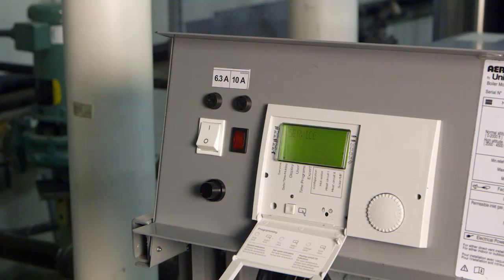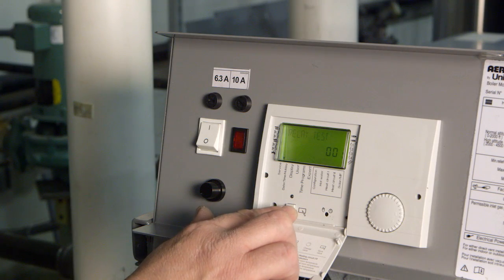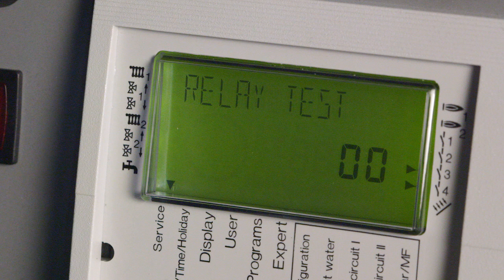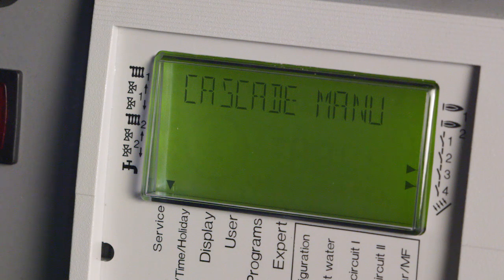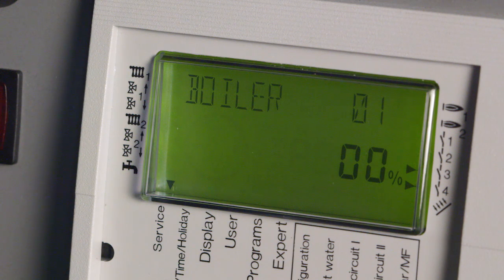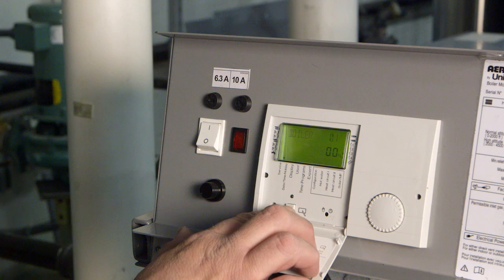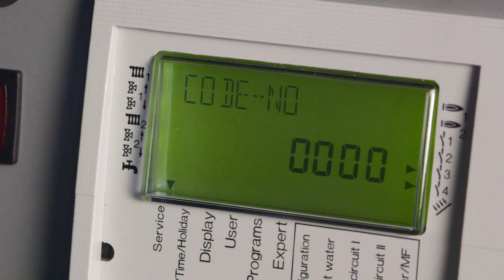Now, press this button to enter the service menu. Relay Test will be displayed. Turn the wheel clockwise until display shows you Cascade Manual. Press this button again to open this level. On the display, it should read Boiler 1 at 0% as shown here. Hit this button. Number code will appear.